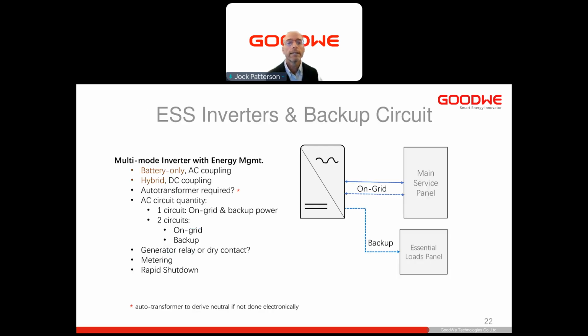The inverters, the ESS inverters, are going to be a battery only if you're doing AC coupling to an existing PV system, or a hybrid, a PV hybrid. In both cases, you need to know whether that ESS inverter includes an auto transformer. Why is that necessary? Well, if you want to back up 120 volt circuits, you need to derive a neutral. That neutral is lost when you no longer have the grid. So you have to derive a neutral from the power that you're exporting, or output, from the inverter.